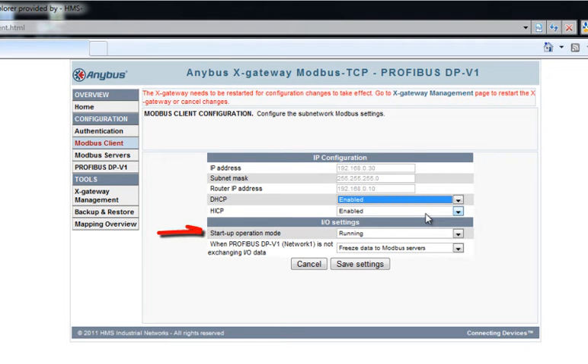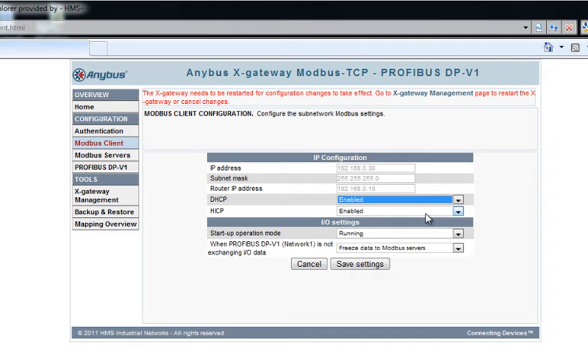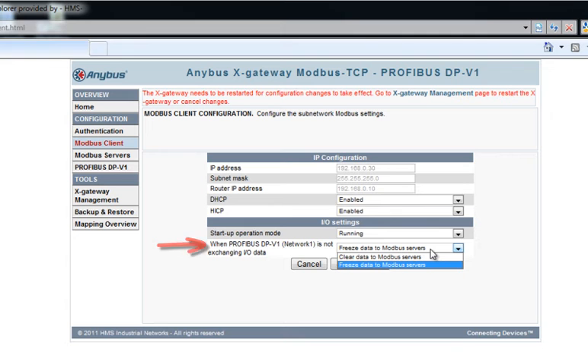Startup Operation Mode indicates how the X gateway should act at startup. In this case, it is set to running, which means that it is waiting for a control word from Profibus before it starts. We can also specify what to do if Profibus is not exchanging I/O data. Either clear data to Modbus servers, which means that it sends zeros, or freeze data to Modbus servers, which means that it keeps repeating the data it sent the last time.